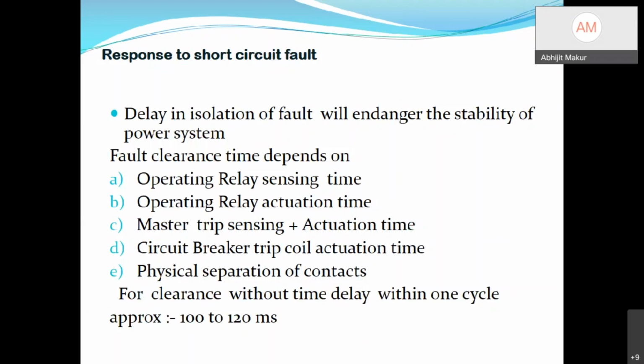See, delay in fault clearance will affect the stability of the system, because fault clearance time depends on the relay sensing time, operating relay actuation time, master trip sensing plus actuation time, then circuit breaker trip coil actuation time and physical separation of contacts. The total procedure requires 100 to 120 milliseconds. Even in a very conservative estimate, it does not take less than 80 milliseconds, because each and every part has its own transient response and that adds up to the delay.